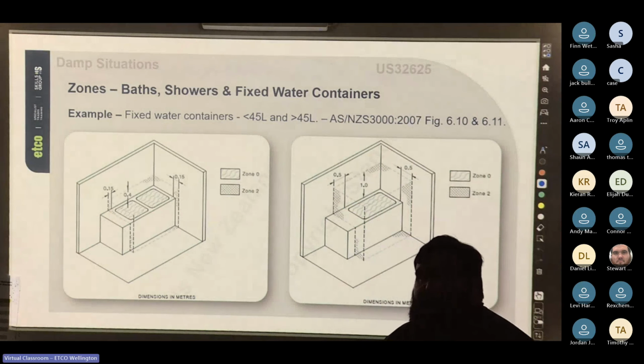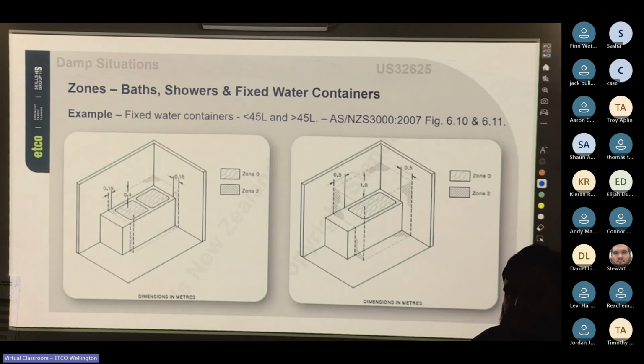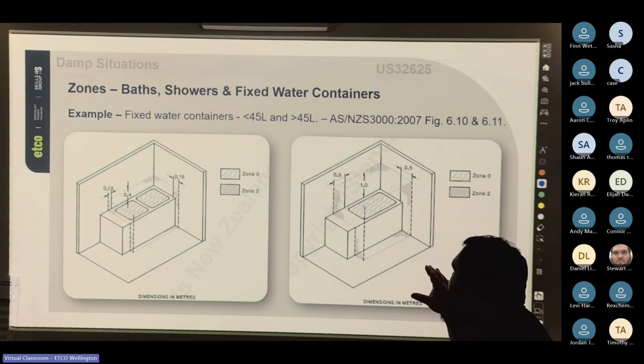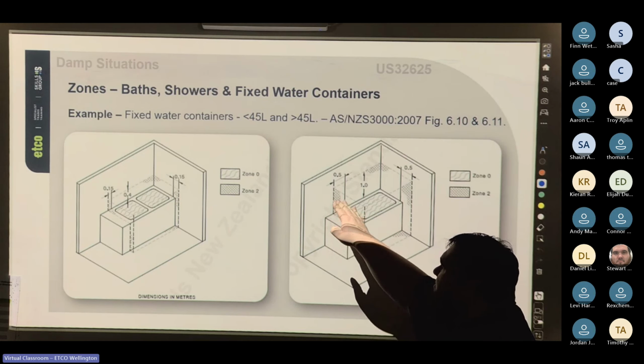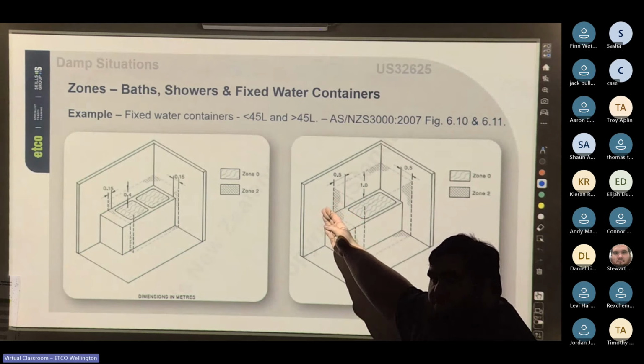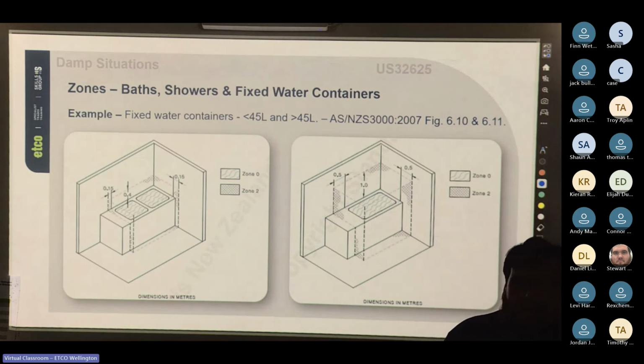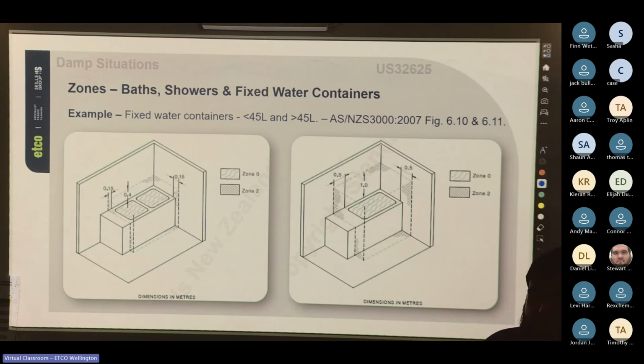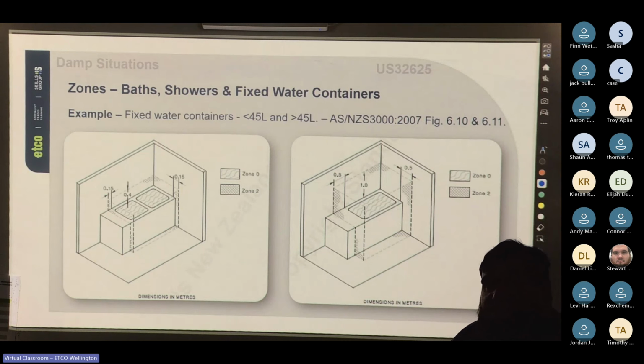It is all about how far you're willing to go to make it safer. Yes, you can do this. If the client asks you to put a socket outlet 300 above the bench, 0.6 metres away from the water container, legally you can do it. But what I would be telling them is, yes, I can put it that close, but do you really want it that close to the water when something might splash out of there? Who knows? Maybe they've got a small dog and they're going to use this sink to wash that small dog. And if anyone's seen any of those dog washing videos on YouTube, they can get pretty feisty, the small ones, and they love to shake.